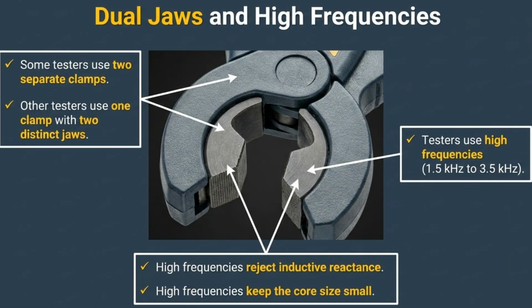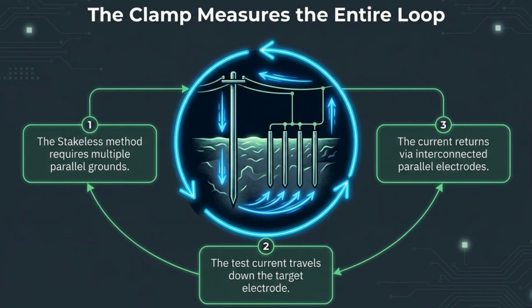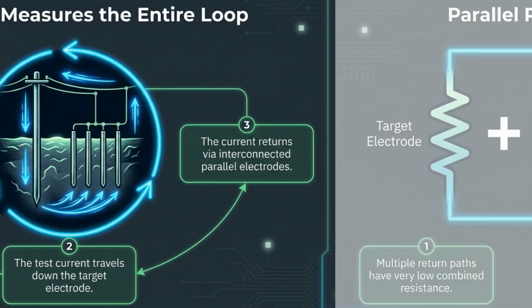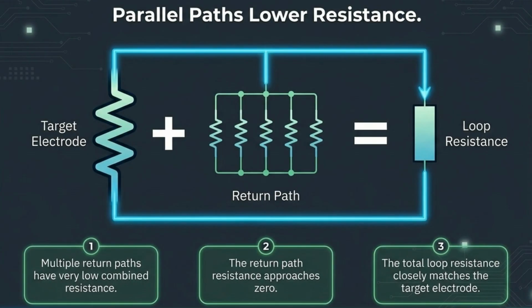These testers often use dual jaws or two clamps to inject high frequencies, typically between 1.5 and 3.5 kHz. This approach helps reject inductive reactance and allows for a smaller core size. This method measures the entire loop. It requires multiple parallel grounds, so the test current can travel down the target electrode and return via the interconnected path. Because multiple return paths exist, their combined resistance is very low, approaching zero. Consequently, the total loop resistance measurement closely reflects the resistance of the target electrode.